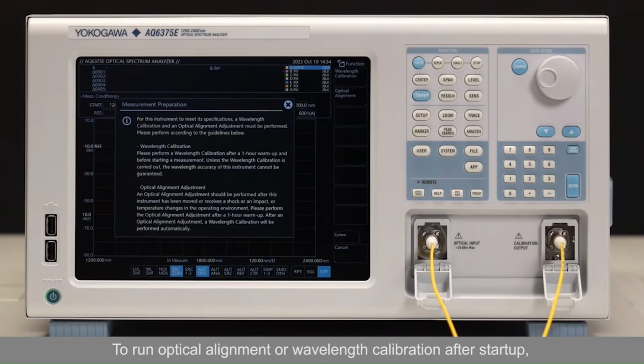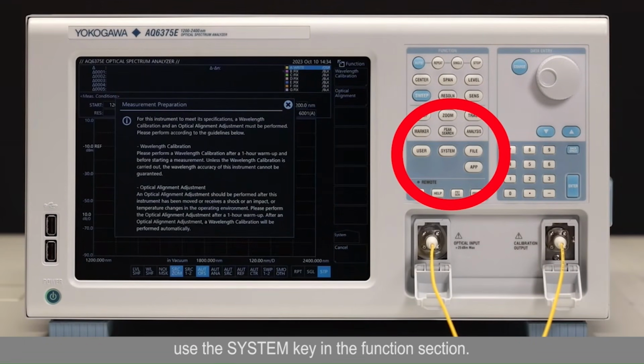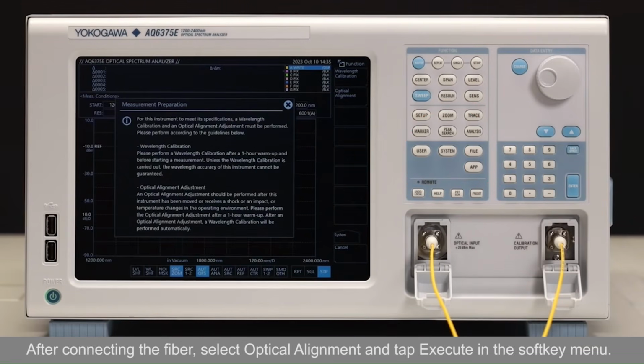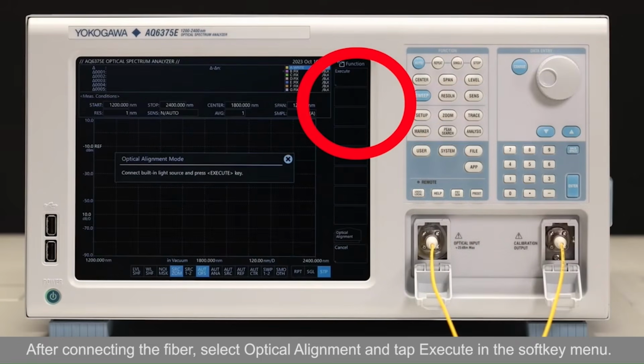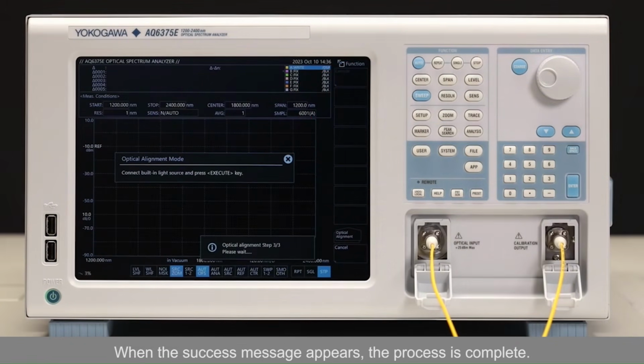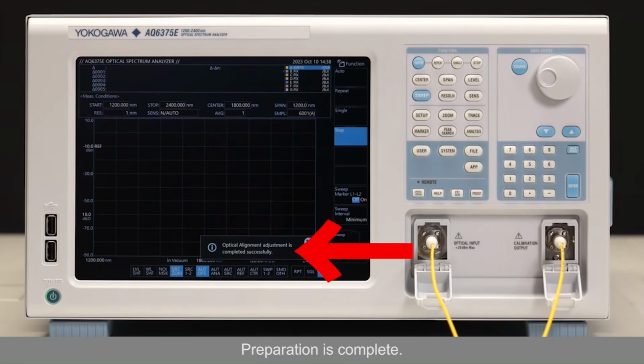To run optical alignment or wavelength calibration after startup, use the System button in the Function section. After connecting the fiber, select Optical Alignment and tap Execute in the Soft Key menu. When the success message appears, the process is complete. Preparation is complete.